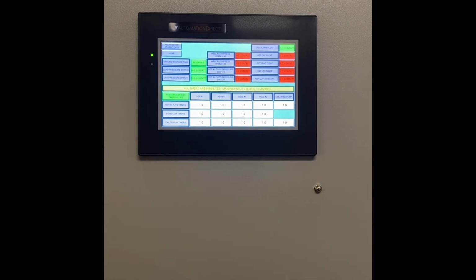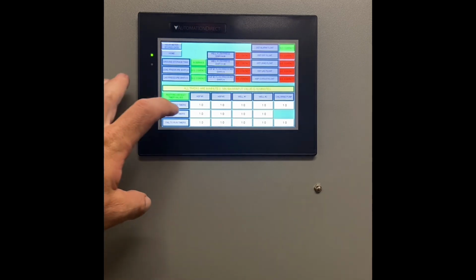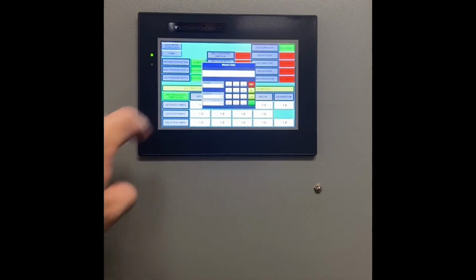Each one of those numbers will bring up a keypad entry so you can change it. So we'll touch high service pump number 1, not in auto, and you'll see the numeric entry comes up. Comes up as a 0, and you can see on the screen that it gives you a maximum allowable of 10. There is no reason that it should take 10 minutes for the low flow or fail to run timers. Those should be on the order of fractions of a minute.